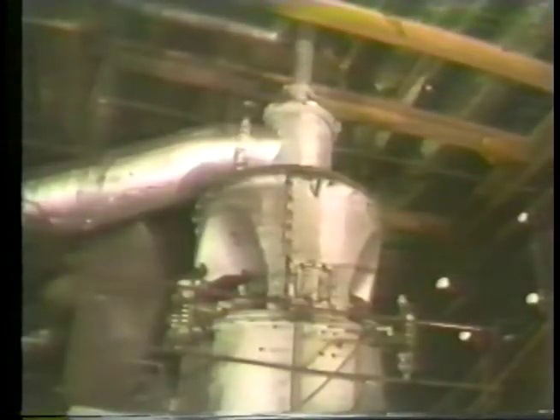His first concern is to provide a means for coal to reach the burners. To do this, many of the steps in the procedures must be repeated several times to get the boiler up to normal firing level. Coal is transported to the burners by primary air that is directed through the pulverizers. As with warming up the boiler, establishing fuel flow must be accomplished gradually to allow all of the fuel to burn completely. Therefore, the operator begins by starting one of the many pulverizers that will supply coal to the boiler.